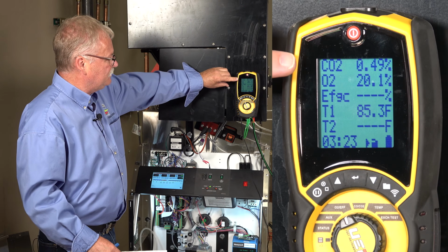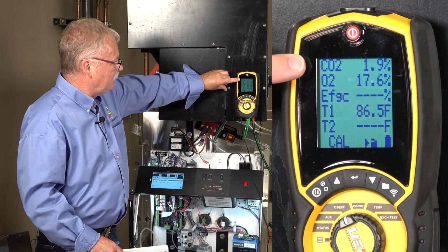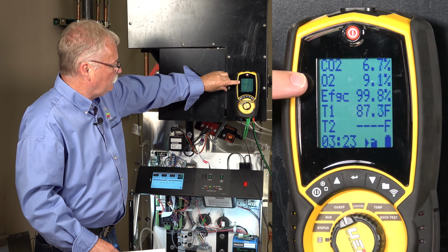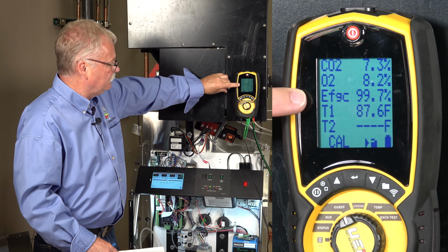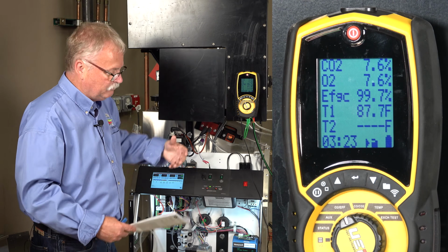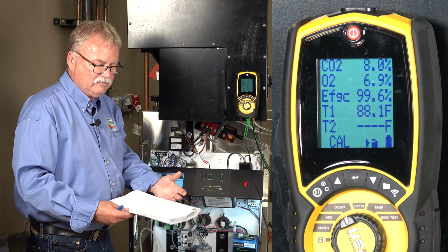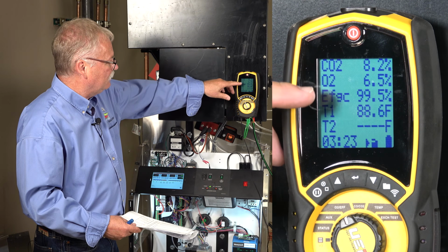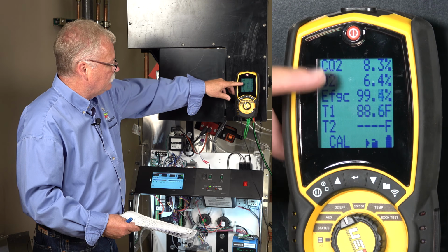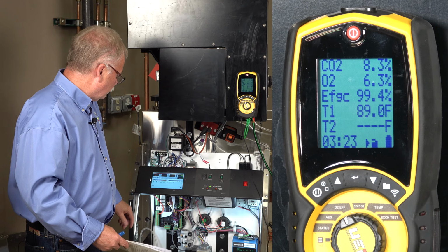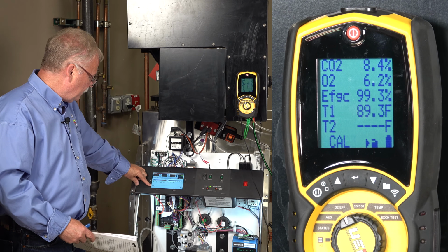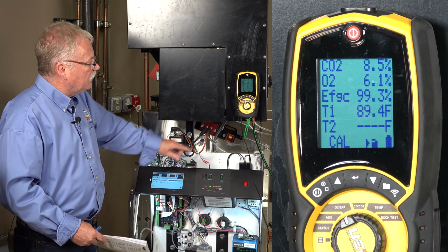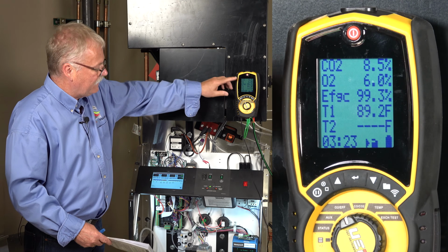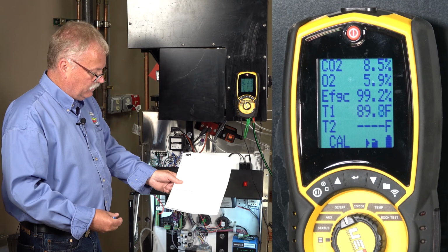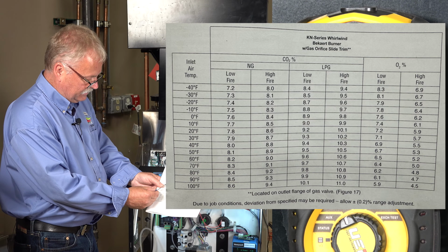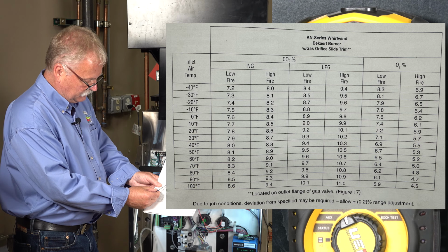Now with it in, you can see the CO2, which is the carbon dioxide. We're reading the percentage of it. Also O2, and this meter is showing me also the efficiency. Right now, since it was basically just lighting off, getting to an even point, everything was making a lot of noise. That's what you heard. You can see the meter jumping up and down right now. So right now we're in low fire, and our CO2 is reading 8.5. In the manual that this company provides, they tell you outside temperature is about 84, right in this range.